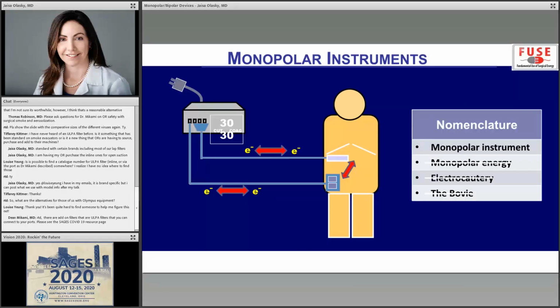The reason we don't say monopolar energy is, as you learned earlier, there's always going to be your two electrodes, and so it's not monopolar energy. There's two electrodes. It's just a monopolar instrument, meaning that the instrument is one of the electrodes, and then the dispersive electrode, the one, again, erroneously called the grounding pad, is your second electrode in this scenario. So as was mentioned earlier, some of the current in this situation would be going through the patient.